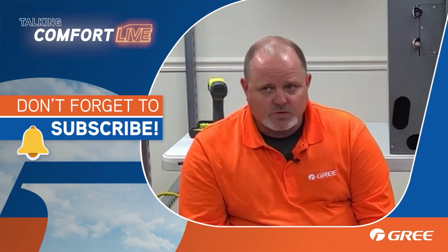Those EEVs, our pressure switches, everything in these machines, being all side discharge, are housed up inside the unit. So your pressure switches are not getting hammered on by the weather. The pressure transducers and EEVs aren't out in the weather. Everything's enclosed. Whether it's an EEV on an indoor or an outdoor unit, it's still accessible, but not weather beaten. I've seen my fair share of EEV failures on units where the EEV is exposed to the weather, and it's usually failures because of moisture infiltration. And it's moisture infiltration from the elements, not from the machine design. Right. So the dependability is there.